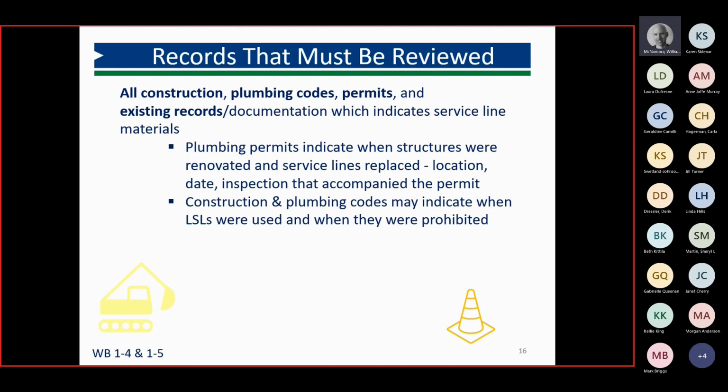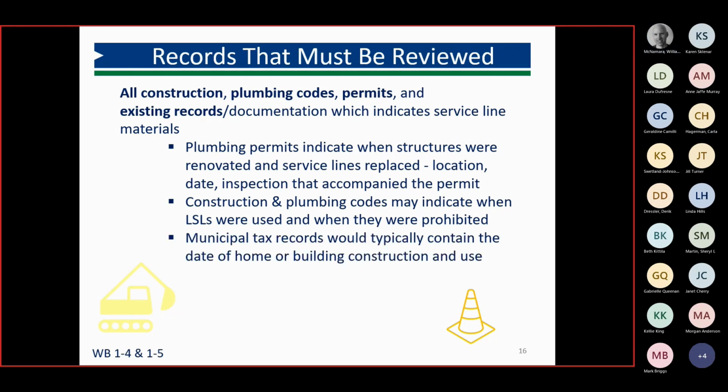Also, construction and plumbing codes can be really helpful for water systems. So we are saying in Pennsylvania that if they have legal documents, ordinances, plumbing codes that went into effect prior to the Pennsylvania lead ban, which Cheryl's going to talk more about, that says that lead cannot be used for service lines after this date, we are allowing that as a standalone method for them to say we do not have a lead service line. So this is going to be a big deal for some systems. There are municipalities out there that have, like, from 1980s on, ordinances saying they cannot use lead. So that could be helpful to them.